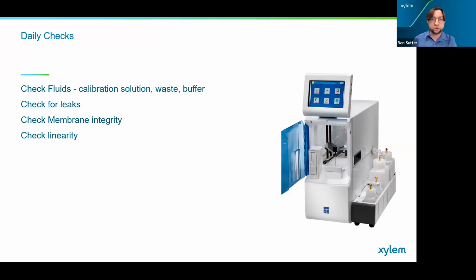Now, when you run these, you're going to get linearity standards and you're going to get an FCN solution, and those are both intended to check the functionality of your instrument. While those aren't completely necessary for the function of the instrument, I would highly, highly recommend that every day you do that to make sure that your instrument is reading linearly and to make sure that your membrane is intact. So those are daily checks.